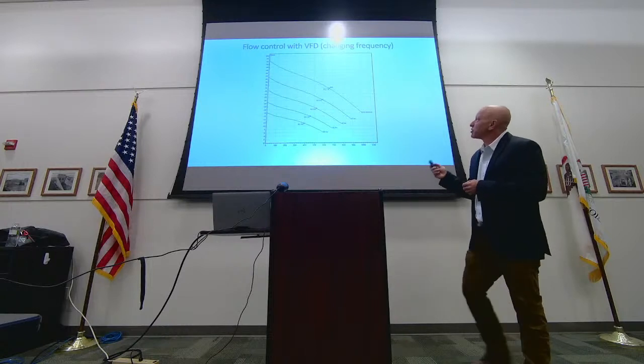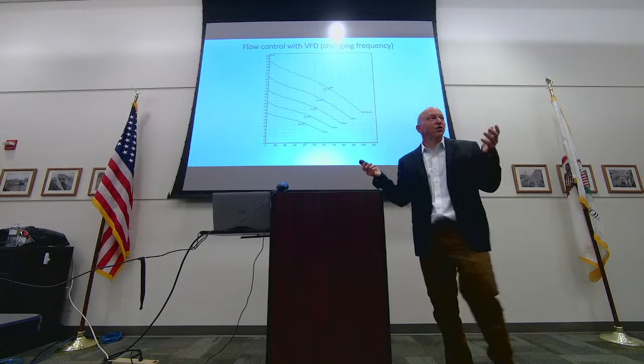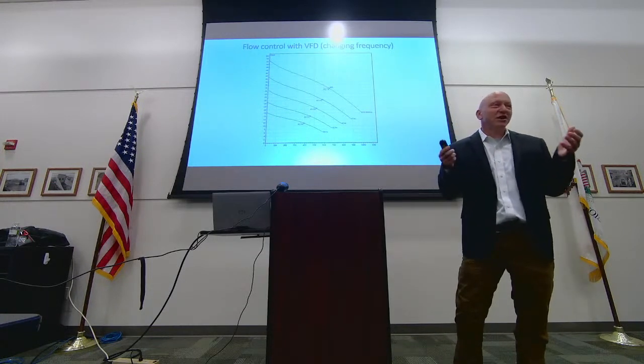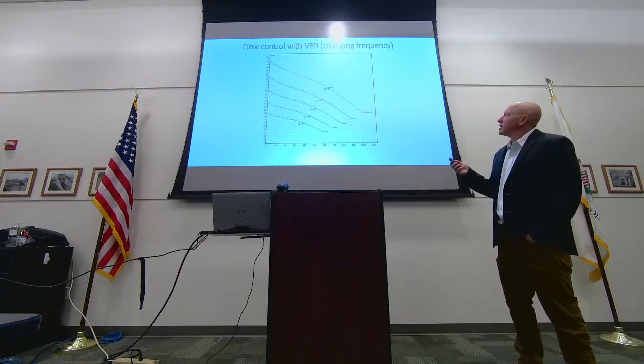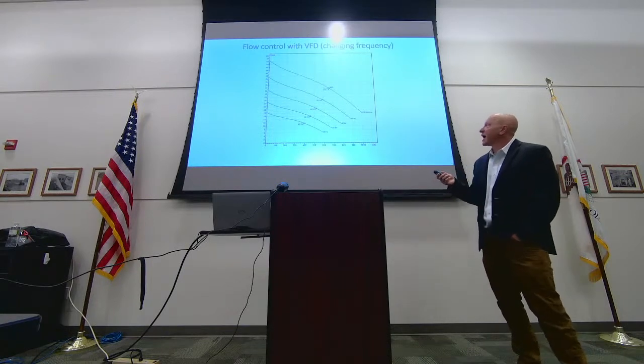And I can't remember the exact math off the top of my head. I used to think, well, if 60 hertz was full power and 30 was half, that you'd get half the flow. That's not how it works. But from 60 to 45, you can about cut your power bill in half.